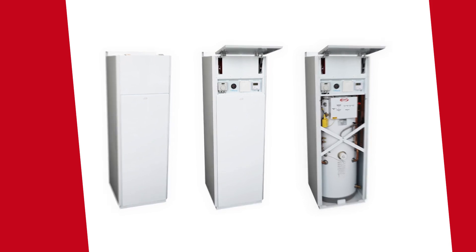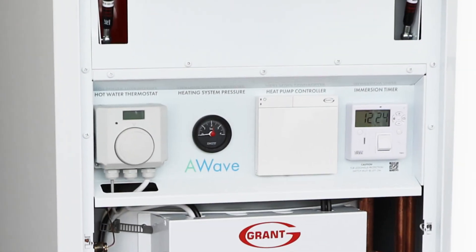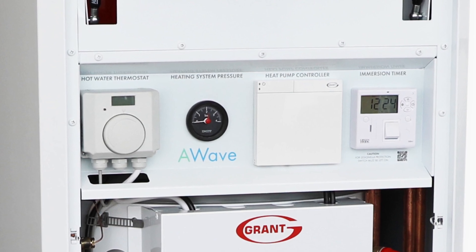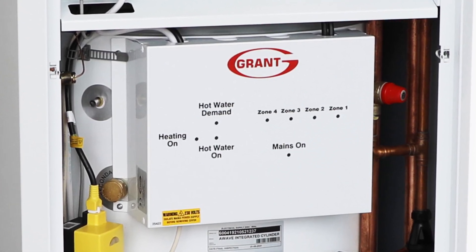Next is the Grant A-Wave integrated cylinder with a compact footprint of 625x595mm and is 1.8m high. The unit is easily incorporated into the design of most modern homes with the system controls accessible by the homeowner if required. The system display pad, digital immersion timer for Legionella, cylinder thermostat and pressure gauge are found behind the top door. The zone options are the same as the previous pre-plumbed cylinder.